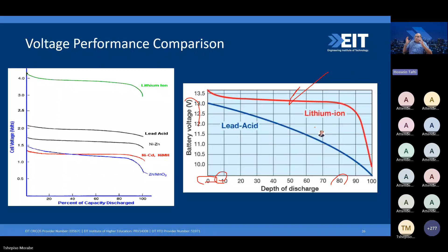These two behaviors could be important factors in the design, because if I want to directly connect my battery system to a grid or to a DC bus, I'm looking for a battery system that provides an almost constant voltage all the time. On the other side, if I'm connecting a lead acid battery, I need to know that its voltage would keep changing based on the depth of discharge, or in other words, the state of charge. So this electrical performance is an important factor in the design of the system.